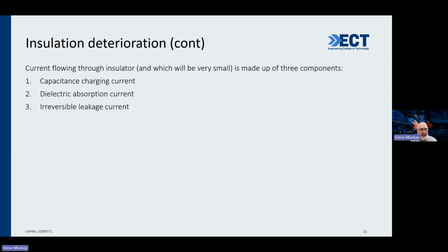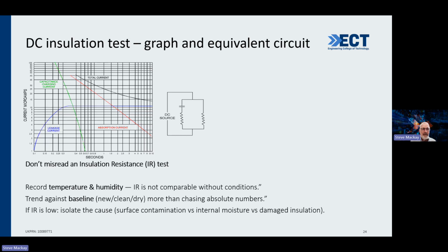And when you're looking at the current flowing through an insulator to actually measure it, it's got three components: the capacitive charging current, the dielectric absorption current, and the irreversible leakage current. So those are the three components. Here's a chart showing you the three components, and that's the test that you'll be using.